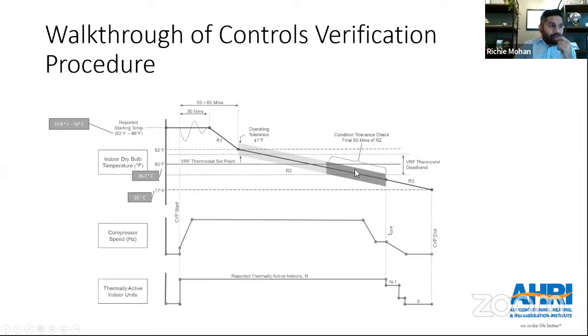And I'll come back to this. It is probably going to be the most important part. After the point when the first indoor unit shuts off, you let the indoor test chamber temperature ramp down until all of your indoor units are turned off, which is perfectly fine. But this dark gray period is the 60-minute period prior to the first indoor unit shutting off.